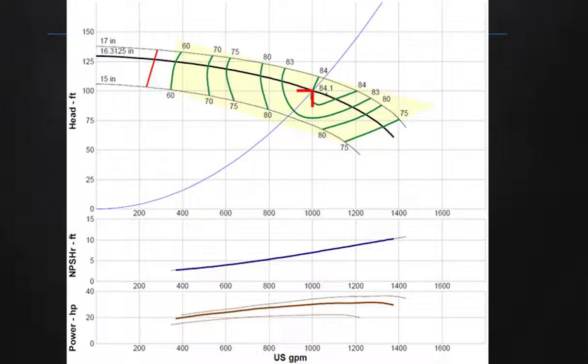Now let's consider a quick analysis of the following pump curve. Notice that the pump curve combines the pressure head for the pump with its net positive suction head, as well as the power usage. And also sometimes the energy efficiency of the pump is also given, and the pump curve is also shown here in a range of values, because it can change depending on variations in the actual mechanical construction of the pump, and also how the fluid interacts with the pump in question.